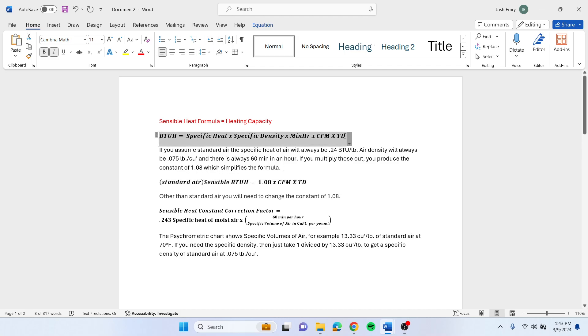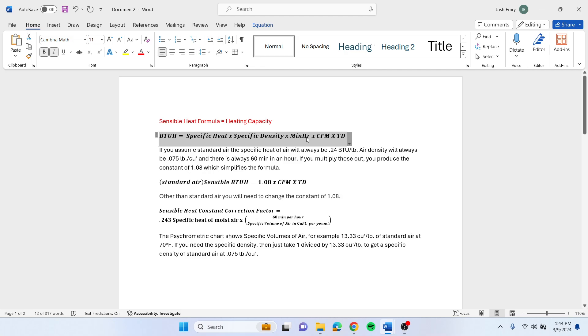Where that came from is this is the actual full longhand version of that calculation. What you have to figure in is your specific heat, which for air is 0.24 BTUs per pound, times your specific density. That specific density changes by the temperature of the air, times minutes per hour which is always 60, times your CFM, times temperature difference.